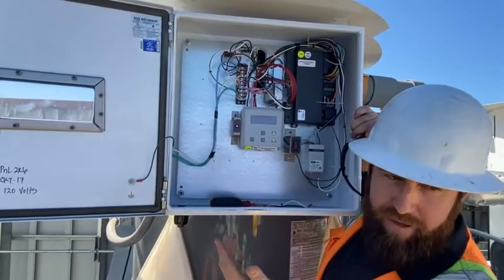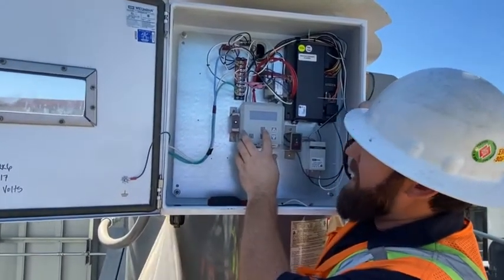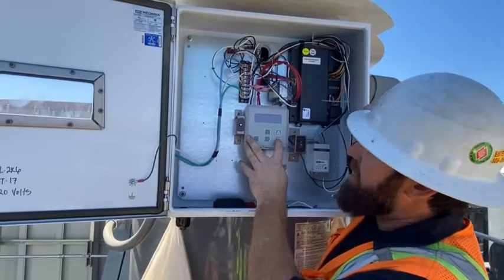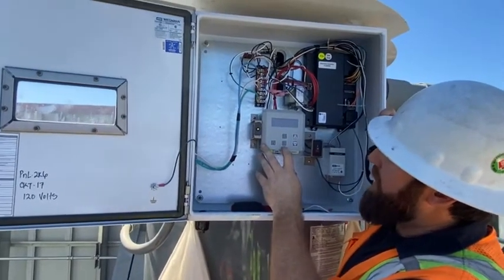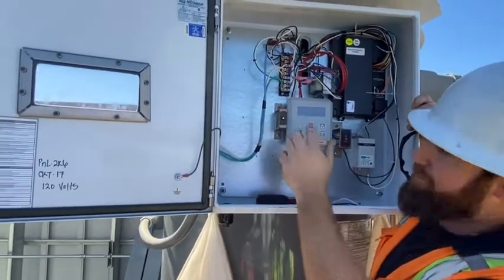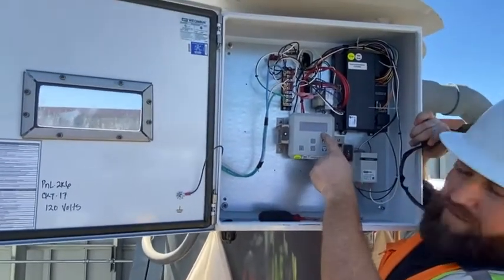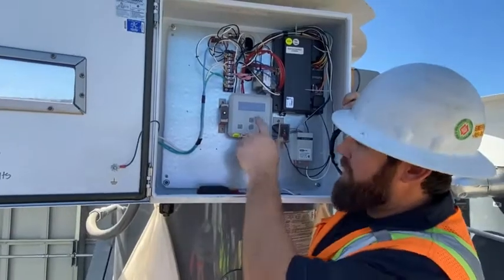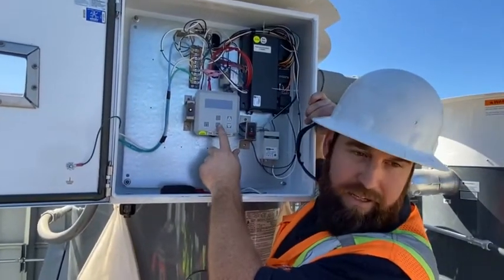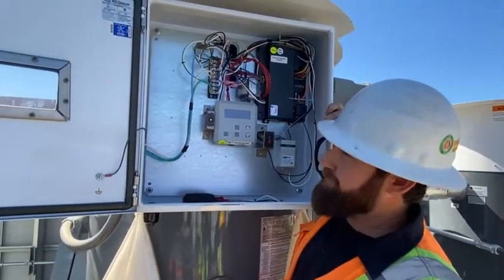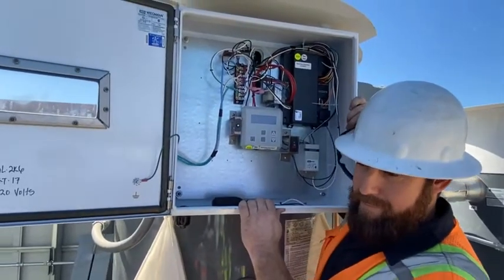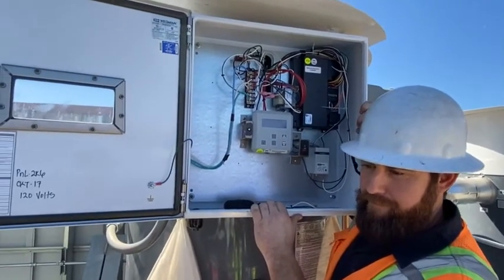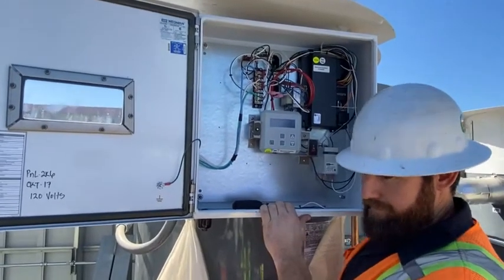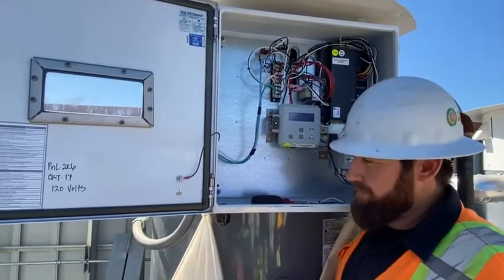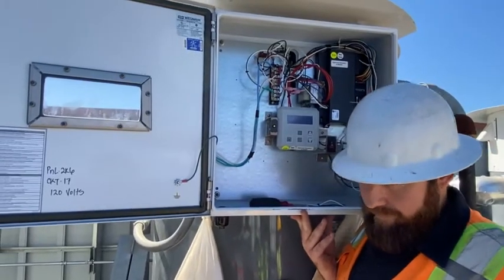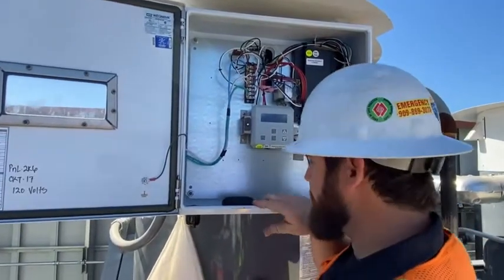To adjust the set point if you need to, you hit the M for menu, go down to settings, click OK. First one up is the set point. You click OK again, the actual number starts blinking. You adjust as needed, click OK again. It sets the set point. We need a minimum of 140 though, okay? You can't go under 140 because we have a storage tank for water. If you go under 140, you could have the potential of growing Legionella, okay? Make sure we keep the set point at least 140. It should be kept at 140 all the time.